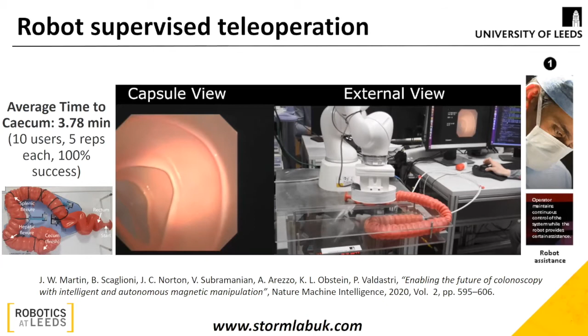The system computes in real time the position and orientation of the endoscope tip and decides how to best move the external magnet to achieve the motion desired by the user. Results from a usability trial involving 10 non-expert users, each repeating a colonoscopy in a training simulator 5 times, showed a completion rate of 100% and a completion time of less than 4 minutes, which is comparable with conventional colonoscopy.